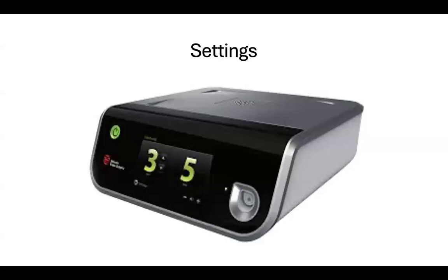Yeah, same thing. Basically, I'm just trying to say that the settings are immaterial. Don't say 3. People say 3 is for coagulation: I'll coagulate the vessel using 3, then I'll cut the vessel using 5. In essence, when you put it on 3, there is definitely going to be more friction generated because the length of the active blade is going to be slightly more. This is just logical.